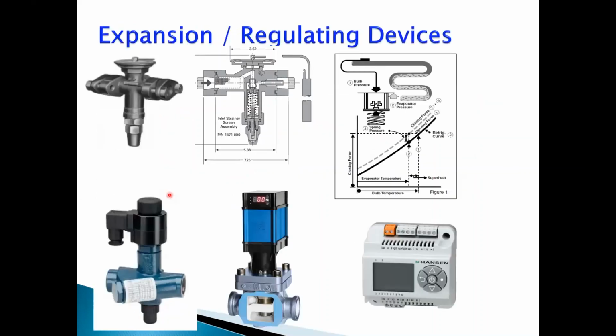So these are the expansion devices which have been used in DX systems. These are the most critical, the most important part of a DX system. As we know, we have a bulb, and we have this diaphragm assembly over here, with the bulb connected here. This bulb is normally filled with a refrigerant combination which operates on temperature. This bulb is connected to the outlet of your evaporator. So depending on the temperature of the evaporator, the pressure of the liquid or gas in the bulb changes, which acts on the diaphragm of the thermostatic expansion valve power assembly. And this pressure works against the spring pressure, or the pressure which is set by using this manual spindle. We normally call this the setting of superheat.